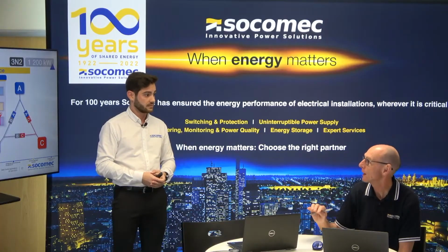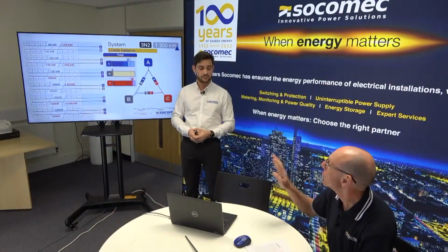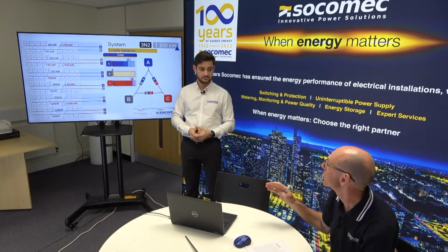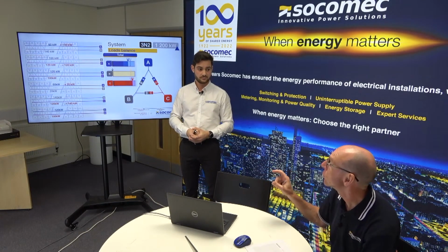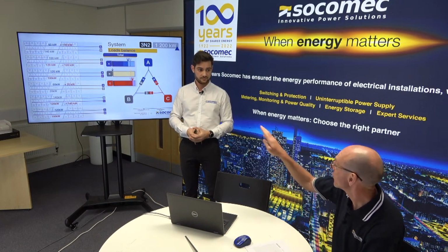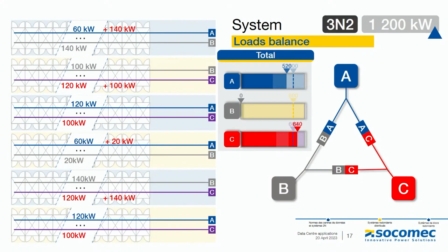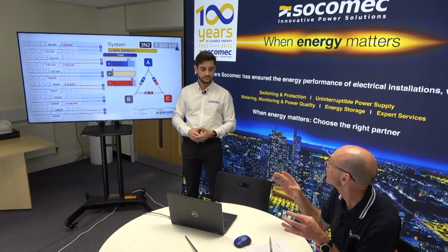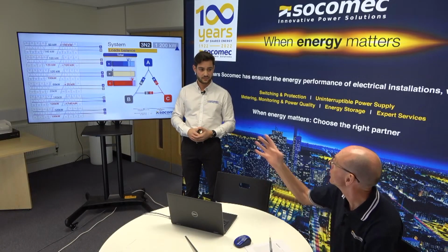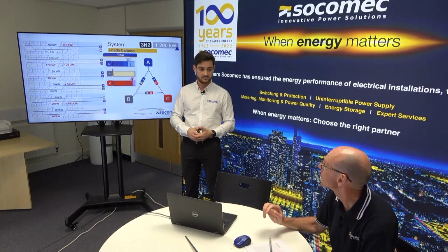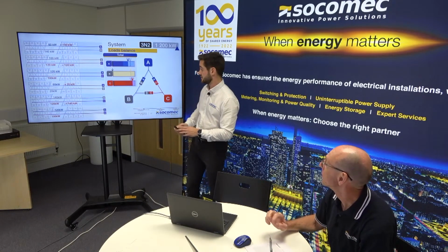Yeah, so obviously, the key point here is that we're still sizing for 1200, which was the architecture at day 1. But when you're looking at a 3N2 architecture as we are here, it's really important that the load is balanced correctly across the 3 power paths. Even though you've still got 1200, if it's not balanced across the 3 and you have a failure, you could have a serious implication of a loss of data. Serious business impact, exactly, yeah.